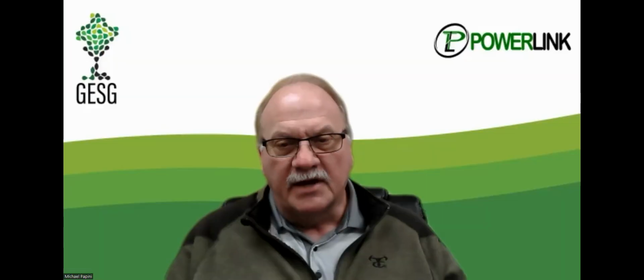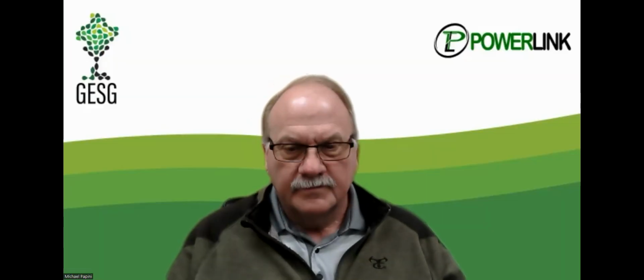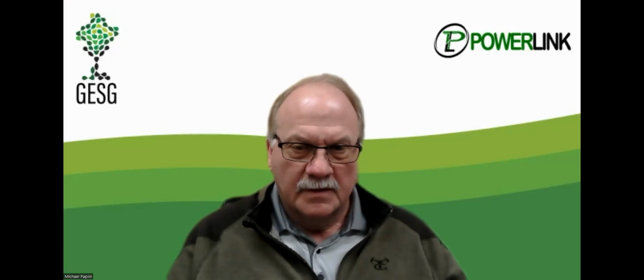To our surprise, that location was actually the best rated, probably because the pumps aren't fluctuating; they're just running this consistent beat the whole time. What was actually the worst power factor number was part of the facility, their banquet facility. Yeah, the banquet, which I guess is because it's got more moving parts, a lot of fans, a lot of air conditioning, a lot of things going in and out that aren't running consistently.